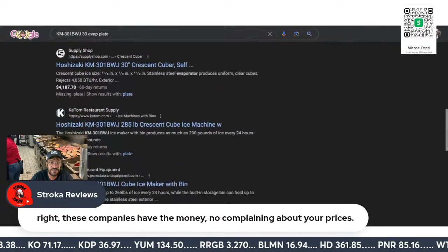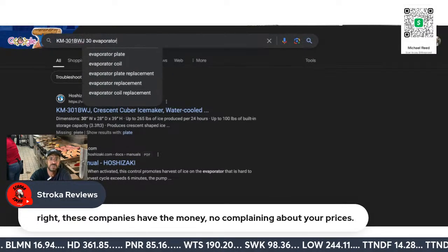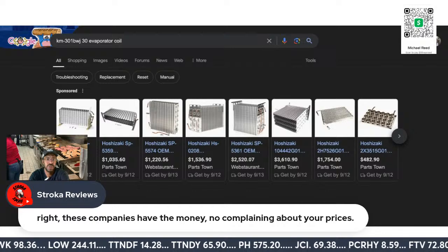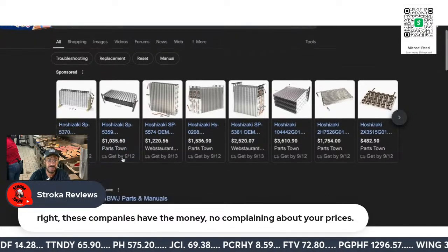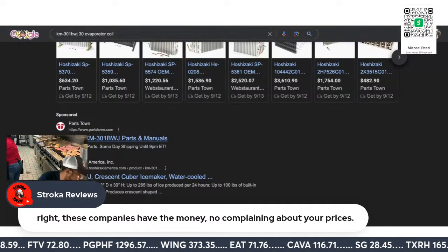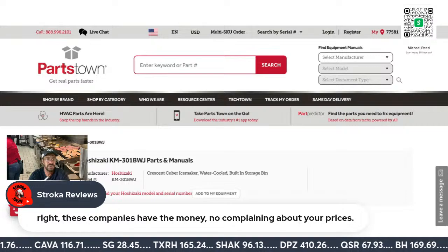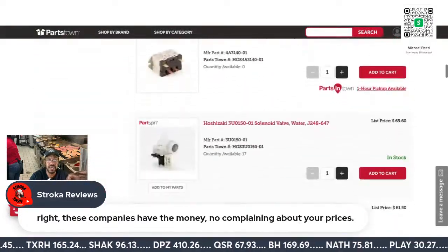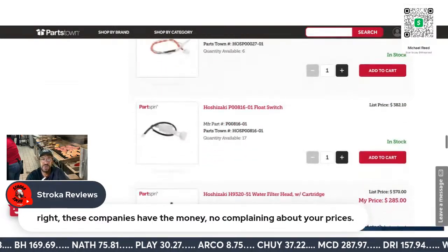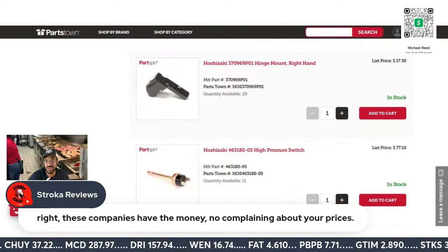So you see the price of it, right? Okay, evaporator coil. So here we go. Here's the coil. Oh. And I swear to you, I hate this machine. This is a pain in the you know what to break the damn thing down and get to. So many damn screws to get to this freaking chill plate. That's the evaporator. So I got a leaking high pressure switch.